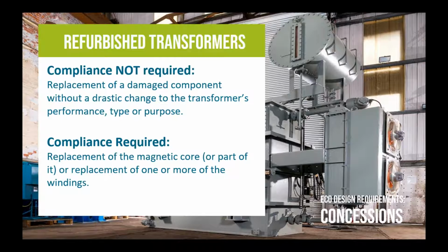In this case, a reassessment would be required and conformity with Tier 2 will be required, so they have to be a Tier 2 transformer if the refurb work includes any change to the magnetic core or one or more of the windings. So there are two different cases here. But obviously, if someone comes to us with a refurb business, we'll assess it accordingly and let you know.